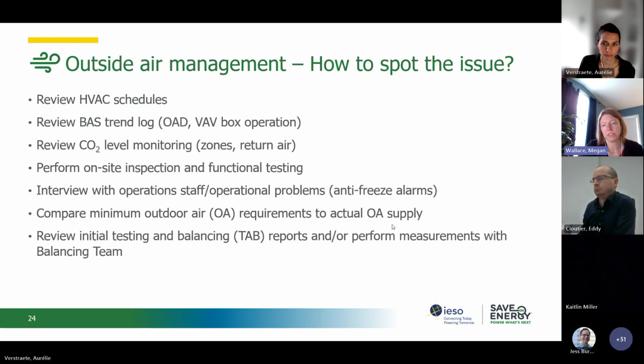Perform an on-site inspection and do functional testing. Do an interview with operations staff and review any problems that they may have, such as an antifreeze alarm. It's a common one. Compare the minimum outdoor air requirements to the actual outdoor air that's being supplied. And review the initial testing and balancing reports, and/or perform measurements with a new balancing team to see what's actually happening in the building.